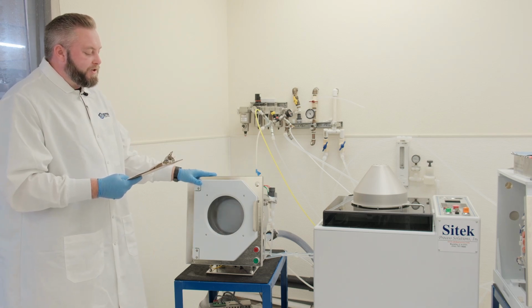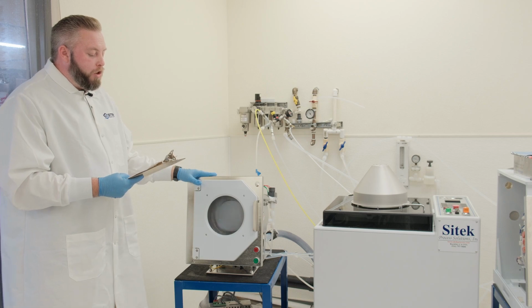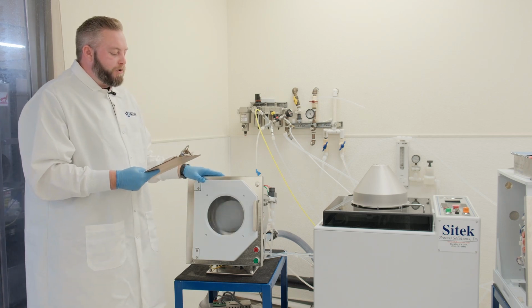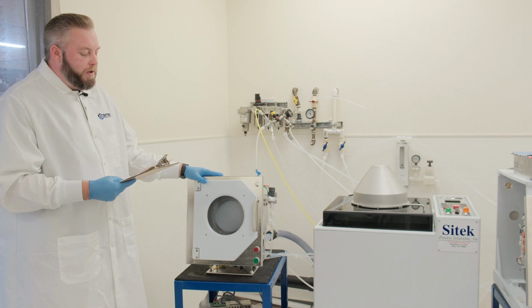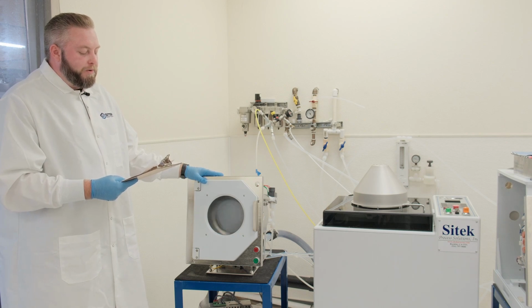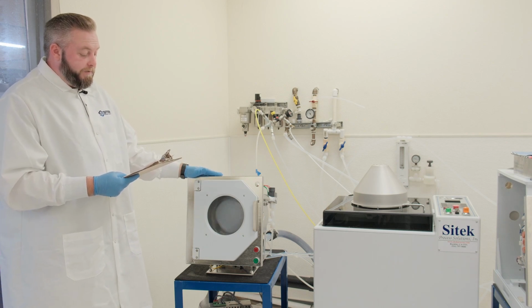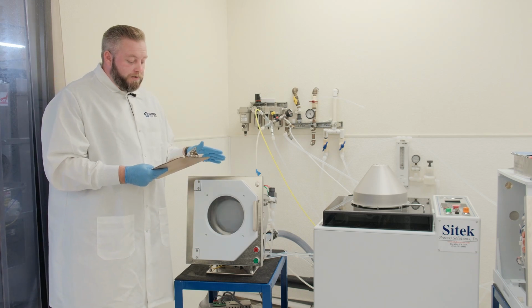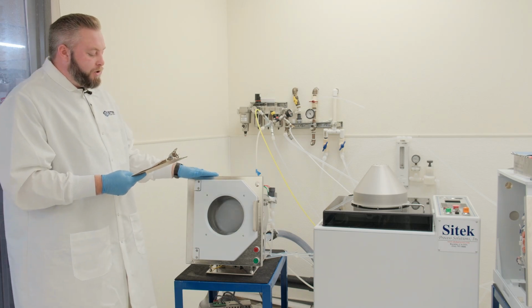In addition to developing a new controller, we also have re-engineered the Foxboro resistivity probe that was discontinued. So since we manufacture these ourselves, we can only keep a small amount on hand. We recommend checking your inventory for a spare, because a resistivity probe is a fail-safe against the contaminated rinse process, and a dirty resistivity probe can lead your SRD to needing to run longer, effectively slowing down your production.